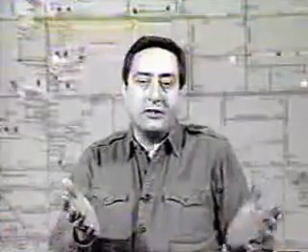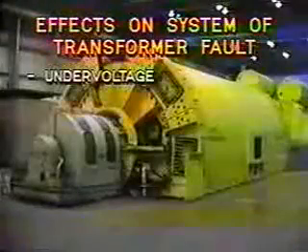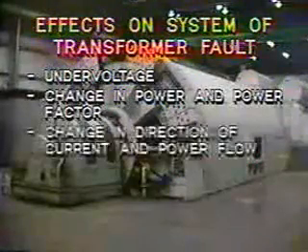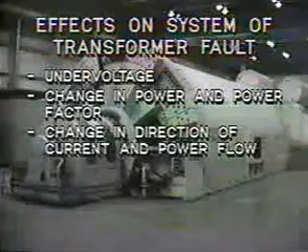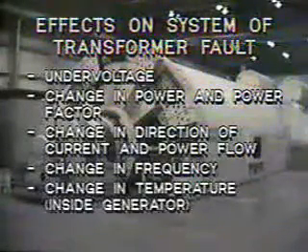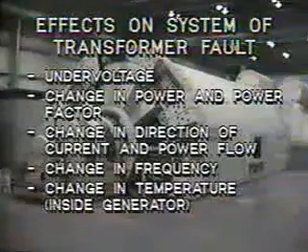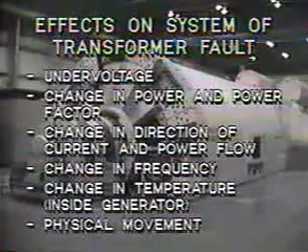For example, a fault in a generator could cause serious change to system conditions, such as under-voltage, a change in power and power factor, a change in direction of current and power flow, a change in frequency, a change in temperature inside the generator, and physical movement — for example, of the generator windings.